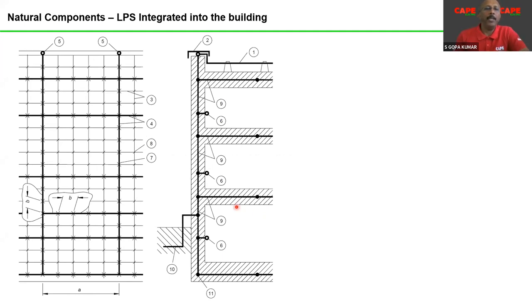What you are seeing in the picture is a building with RCC. It's an RCC building, maybe several floors, a multi-floor building. At the top of the building, you have the air termination, which is always exposed because lightning must hit the air termination. And probably some covering for the parapet. I have taken the picture from the standard. That is why actually in India, we don't have the habit of covering the parapet with this kind of a conductor, but we have the habit of making a metallic handrail on the parapet. If you have a metallic handrail on the parapet, the metallic handrail will do the job of air termination.